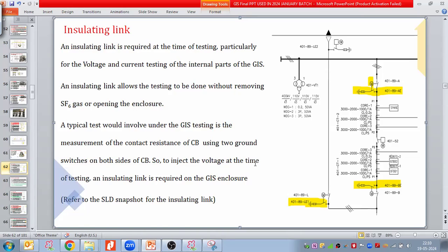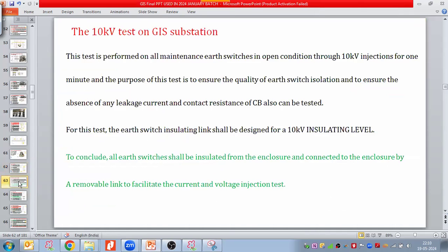To inject the voltage at the time of testing, an insulating link is required on the GIS enclosure, right? So when you prepare the drawing, please indicate the insulating link with your earthing switch as well. So this test is performed. This test is performed on all maintenance earthing switches in open conditions through 10 kilovoltage injection for 1 minute, and this is the 10 kV test on the GIS substation. This is also one test. So this 10 kV test is performed on all earthing switches, maintenance earthing switches in open conditions through 10 kV injection for 1 minute.